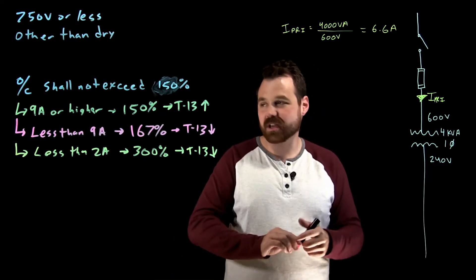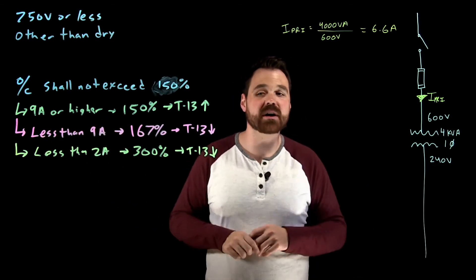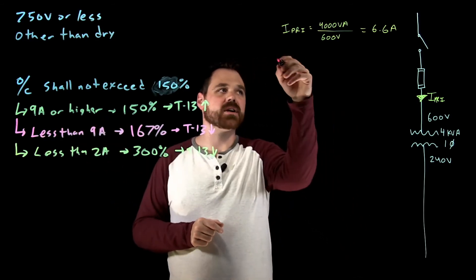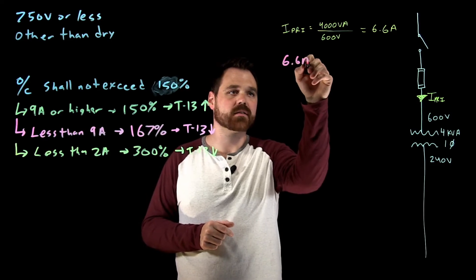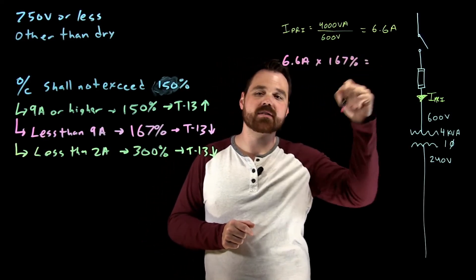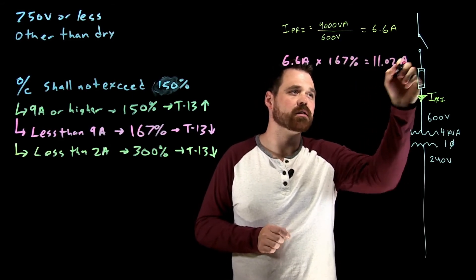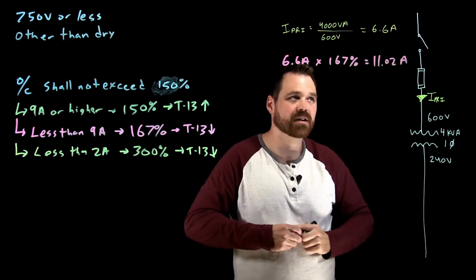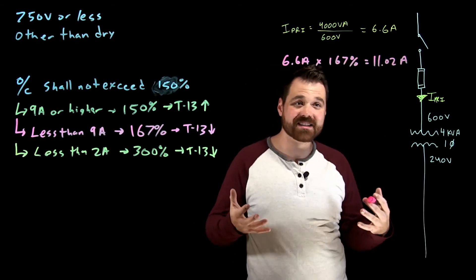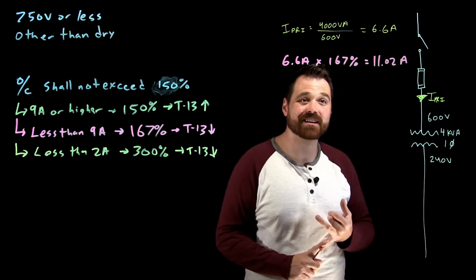So that means I'm less than nine amps, which gives me an option. It tells me you can take your 6.6 amps times it by 167%. In this case, that would give us 11.02 amps. Awesome. From dealing with fuses in that size, there's probably an 11 amp fuse available. So I'm going to take the 11 amp fuse.